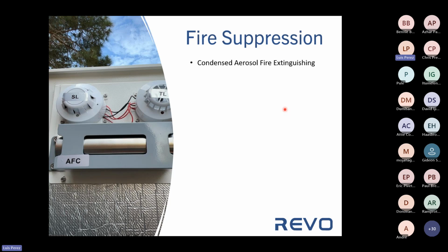So we have three levels of thresholds, if you want to call them. The first one is the temperature ramp. We measure the temperature of the cells 10 times per second. If the temperature gradient of the cell increases above a certain parameter, the system will trip. If it still continues to increase while the system is tripped, then the fire extinguishing system will be activated.